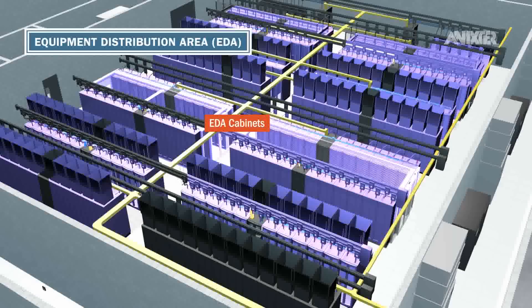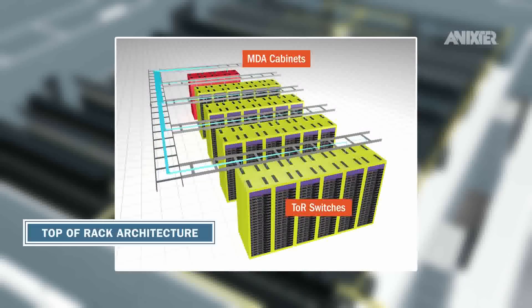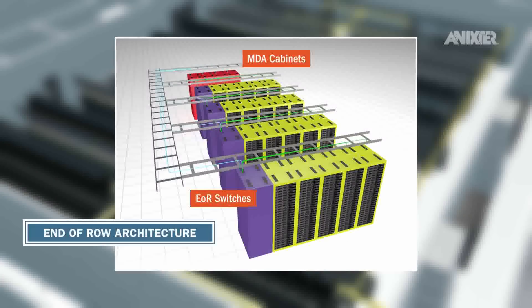In general, top of rack architectures are better suited for data centre environments requiring low latency and high performance server connections, where end of row and middle of row architectures look to optimise cost and flexibility.